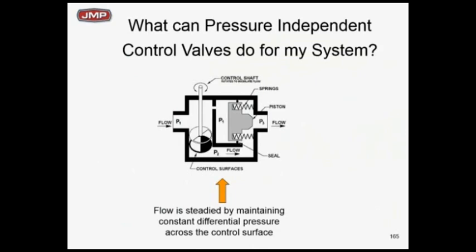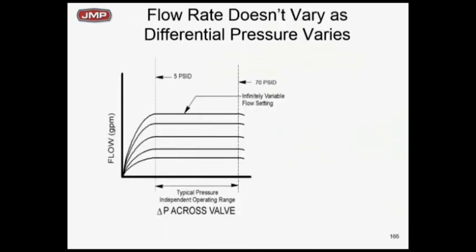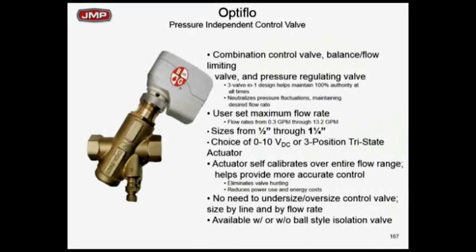So I'll start tying all this together a little bit. What can pressure independent control valves do for my system? I kind of jumped ahead of myself, but basically between 5 pounds and 70 pounds, I'm going to keep a constant flow no matter what the differential pressure does. My control valve is going to stay in the same position. I'm going to get your delta Ts up. This is a product we have. I don't want to go through it too much right here, but the basic idea is we give you full stroke, no matter what the setting. You can set the total flow limit on these, and they read in GPM.